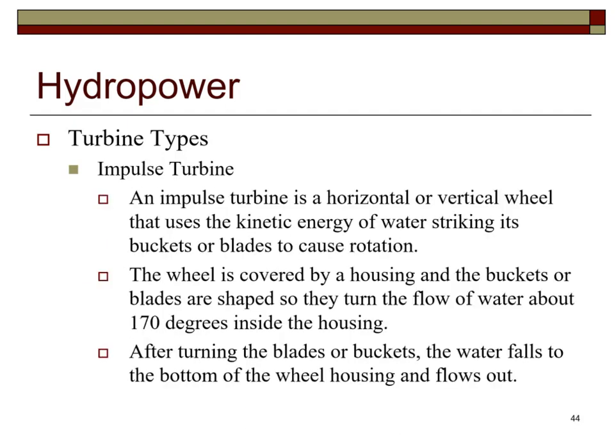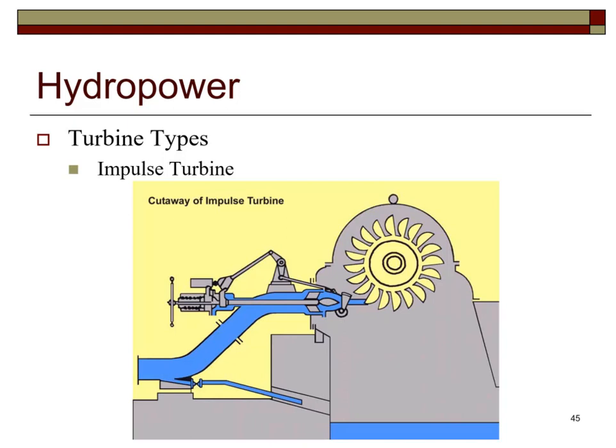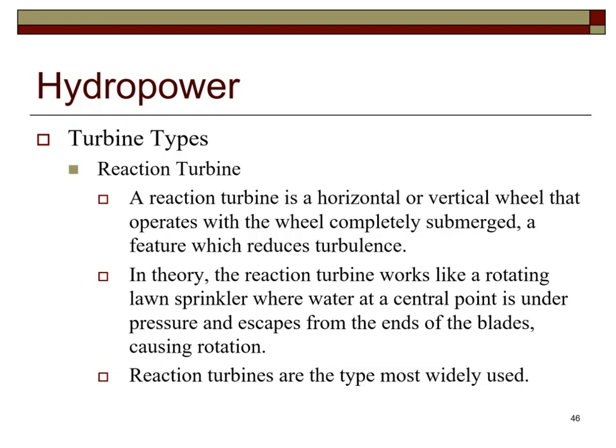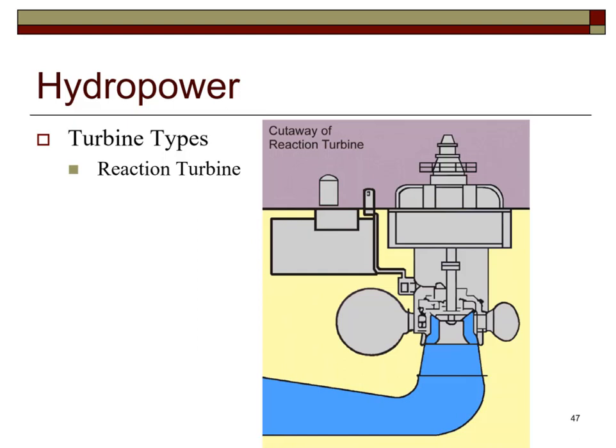An impulse turbine is a horizontal or vertical wheel that uses the kinetic energy of water striking its buckets or blades to cause rotation. The buckets or blades are shaped to turn the flow of water about 170 degrees inside the housing, after which the water falls and flows out. A reaction turbine operates with the wheel completely submerged, reducing turbulence. It works like a rotating lawn sprinkler—water under pressure at a central point escapes from the ends of the blades, causing rotation. Reaction turbines are the type most widely used.